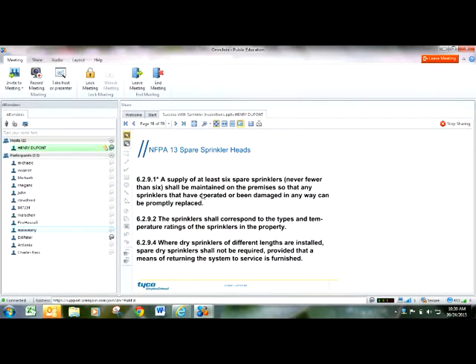I mentioned spare sprinkler heads a little while ago. Every sprinkler system is required to have a spare stock of sprinkler heads for the building. The minimum requirement is 6. The sprinkler heads have to correspond to the type of sprinkler heads within the facility. Furthermore, you have to have a sprinkler wrench in the head box for that sprinkler head. Where you have a building with nothing but dry pendant sprinkler heads, NFPA 25 realizes that every one of those dry pendant sprinkler heads is going to be a different length, and there's no reason to keep a spare stock of them around, but you have to have means to put a temporary sprinkler head in that dry pendant if it goes off. So if you're out on your inspections and you see a building with a variety of different types of sprinklers, and some of them are dry pendant sprinkler heads, it's not a requirement per NFPA to keep a spare dry pendant sprinkler head with that head box.